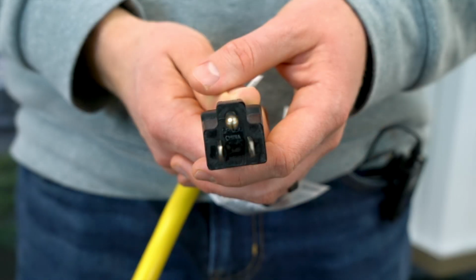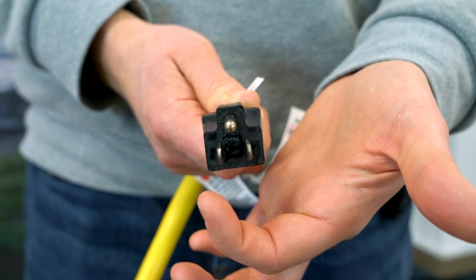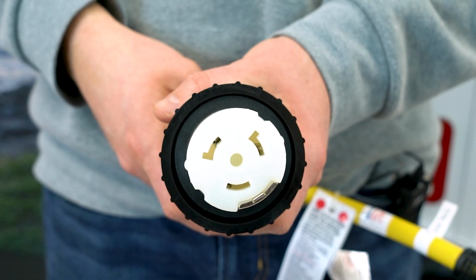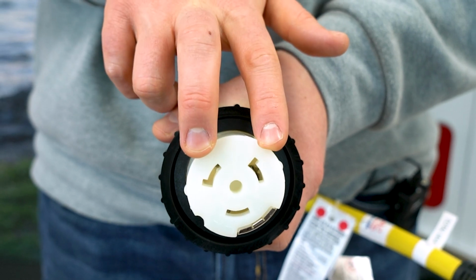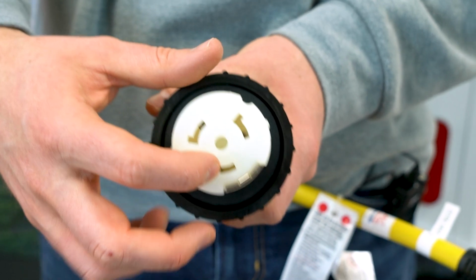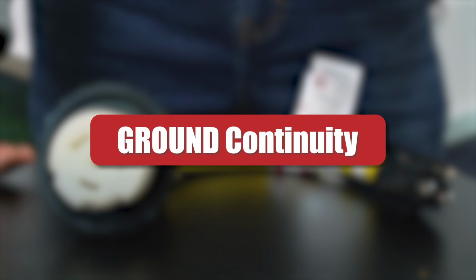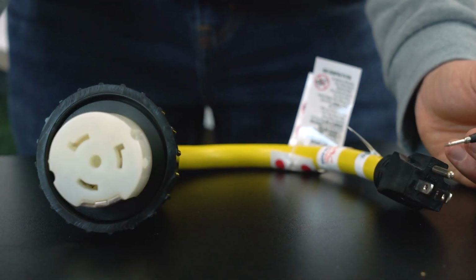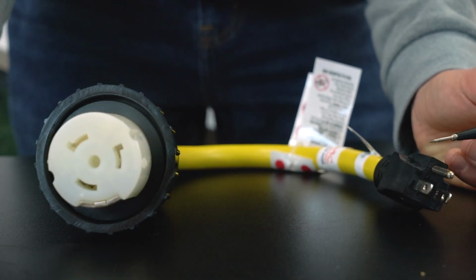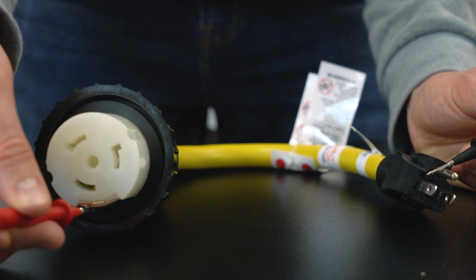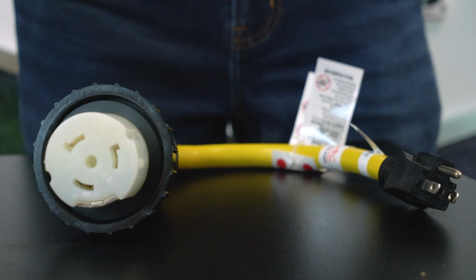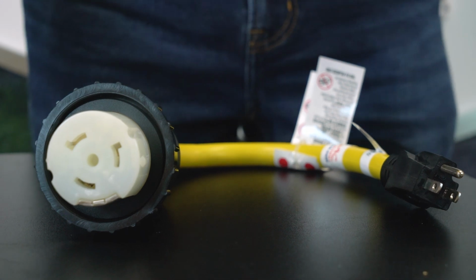Identify the wires or connections on the adapter. On the NEMA 5-15 plug side, one hot, one neutral, and one ground. NEMA SS2-50 receptacle side, which has two hots, X and Y, one neutral, and one ground. Check continuity on the grounds. Touch one probe to the ground prong on the NEMA 5-15 plug. Touch the other probe to the ground slot on the NEMA SS2-50 receptacle. Your multimeter should read a near zero value or beep if in continuity mode, indicating the ground is properly connected.